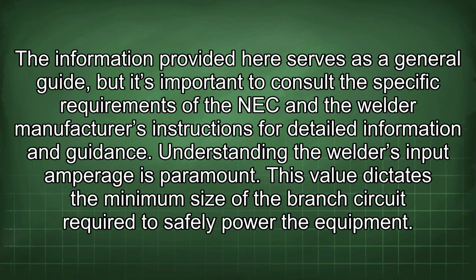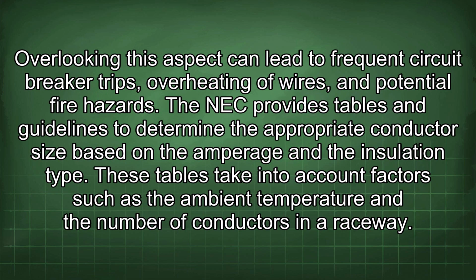Understanding the welder's input amperage is paramount. This value dictates the minimum size of the branch circuit required to safely power the equipment. Overlooking this aspect can lead to frequent circuit breaker trips, overheating of wires, and potential fire hazards. The NEC provides tables and guidelines to determine the appropriate conductor size based on the amperage and the insulation type.